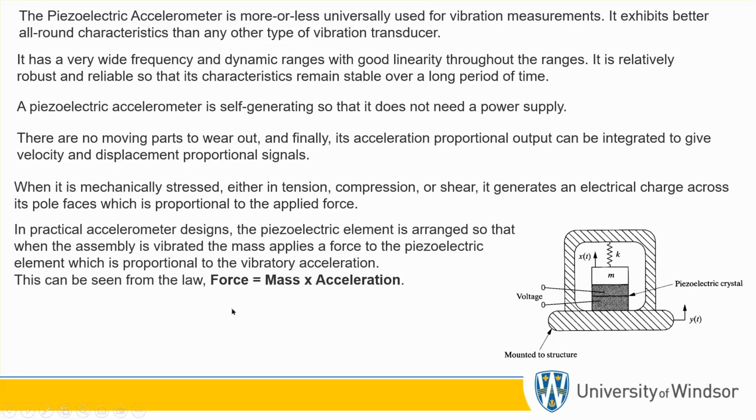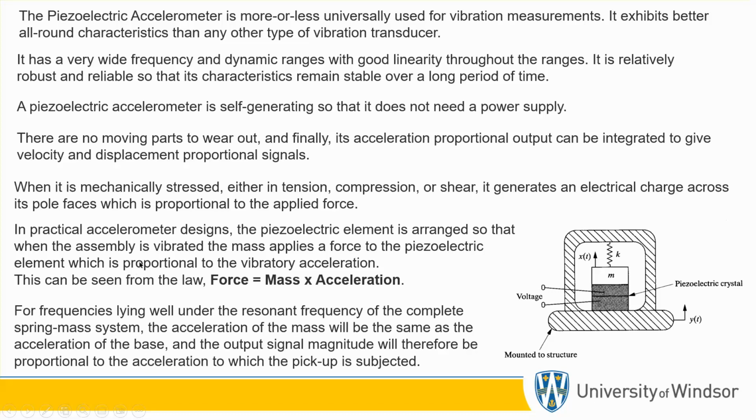And when this casing accelerates or vibrates up and down, this mass will squeeze this crystal, and then stretch it, or relieve it from being squeezed. That's why it generates a voltage.